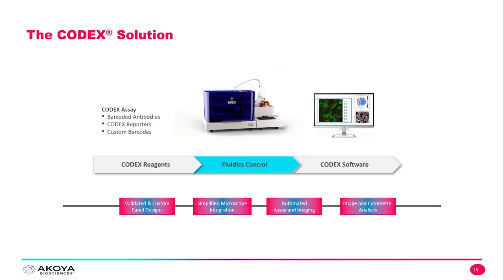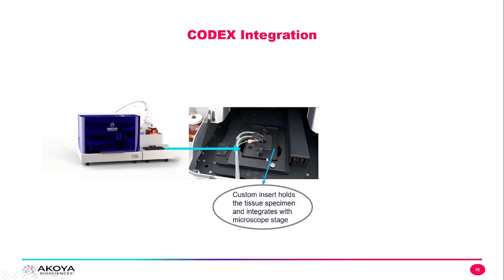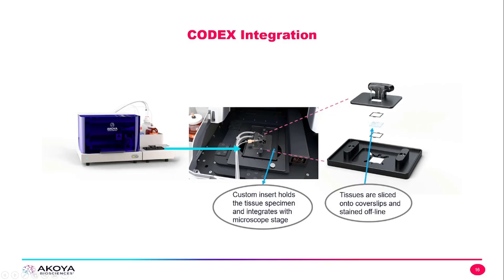The next step of the CODEX solution is the fluidics control, which includes all of the automation necessary to run both the fluidics of the instrument as well as the microscope. The CODEX integrates with the microscope — the fluidic lines lead to the stage, and the custom insert holds the tissue specimen and integrates with the microscope stage. The tissues are sliced onto cover slips and stained offline, and they fit between two gaskets. This whole CODEX insert sits on the stage of the microscope.